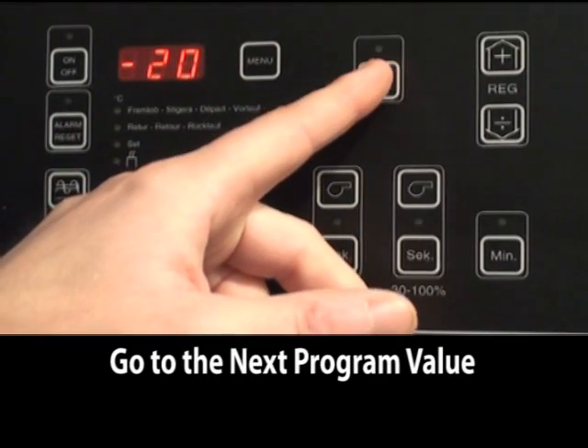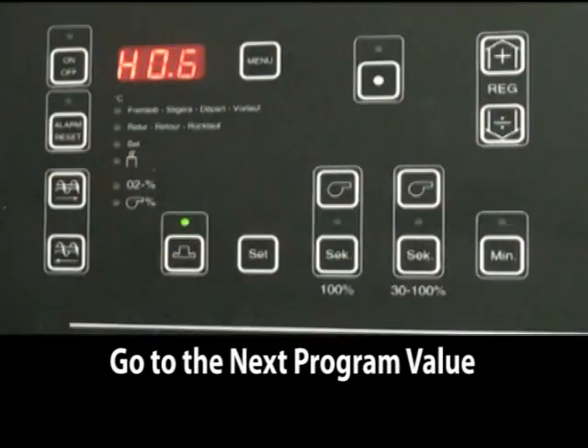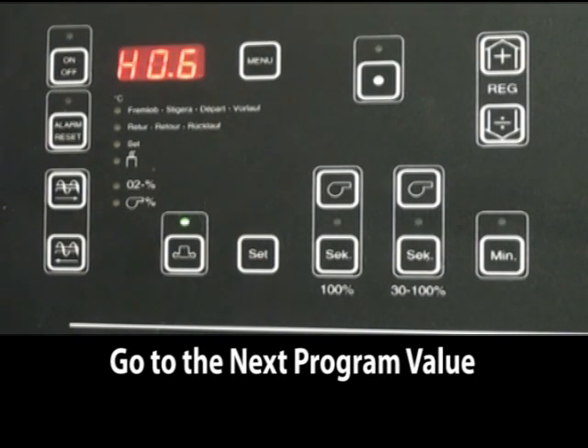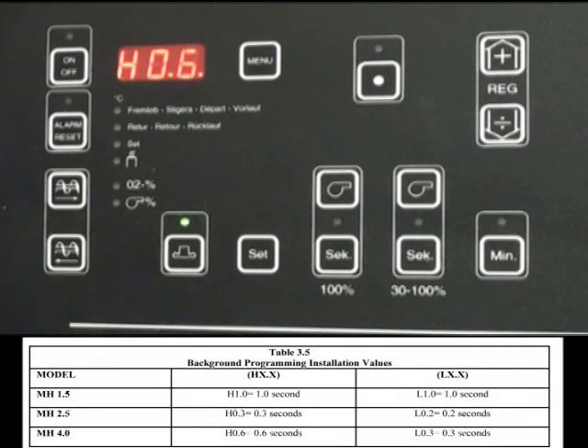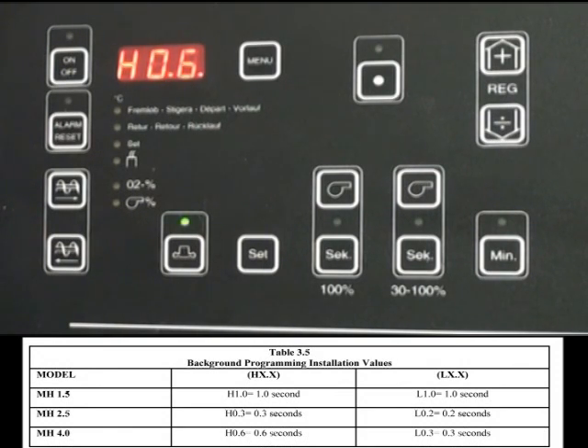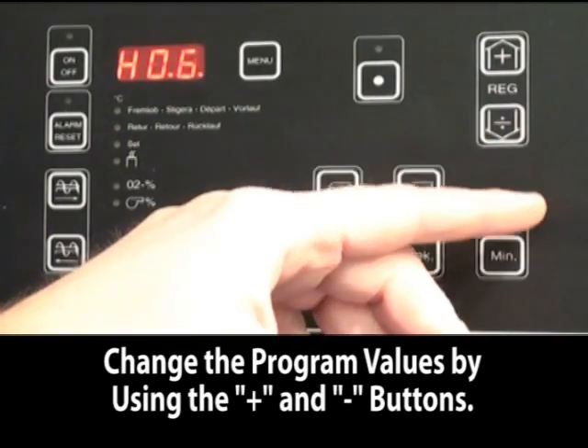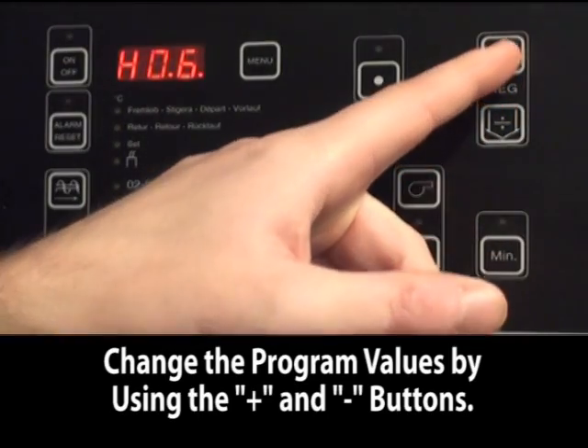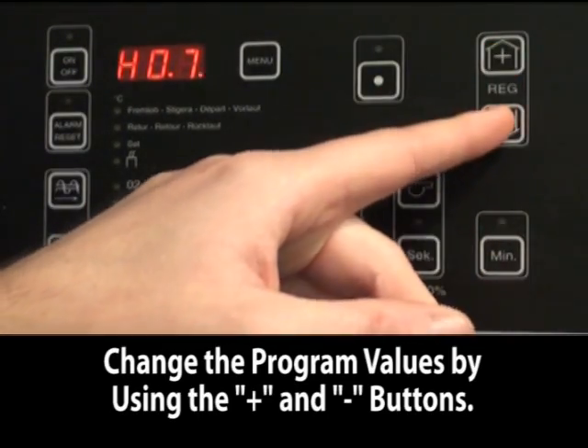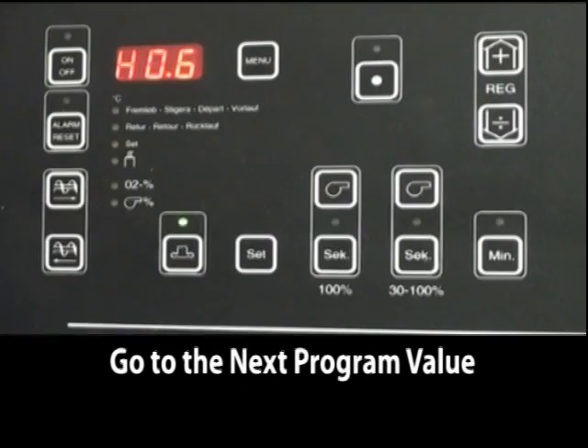The next setting is the auger running time in high output mode. This can be either 1, 0.6, or 0.3 seconds depending upon the boiler. To change any settings, use the plus or minus button.